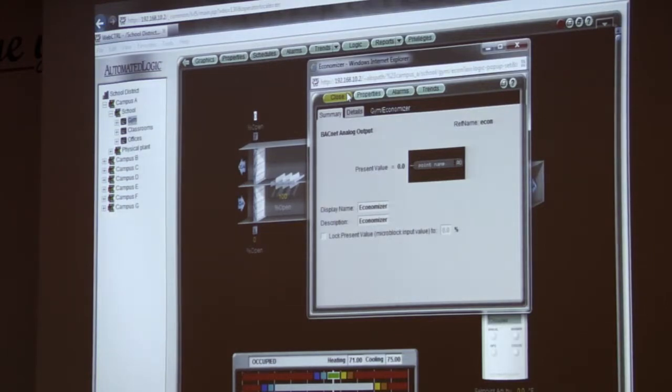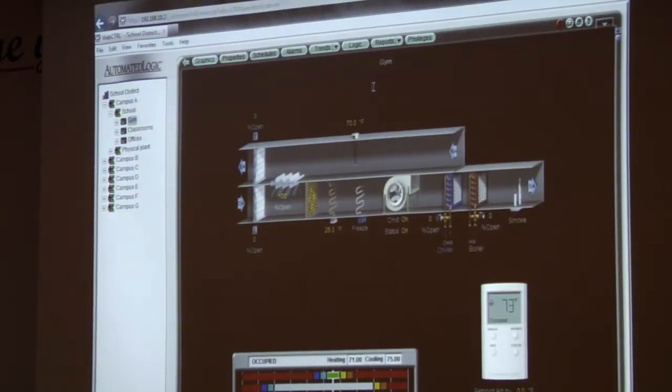So we're going to use a different method of troubleshooting. The first step was my return temp isn't right, and because I've used the system a little bit, I do understand that if my return temp isn't right, the unit believes that it's too cold and it may close my outside air dampers. We're going to go in and go find out why the outside air damper isn't open. We're going to use a different form of troubleshooting. Right? So I'm going to hit close. All right? And I'm going to go through my logic page. Right? My economizer. Telling my economizer to go open. Is this an input or an output? Output, obviously, right? We're going to send a signal and tell it to do something different, right? We know that it's the economizer damper.